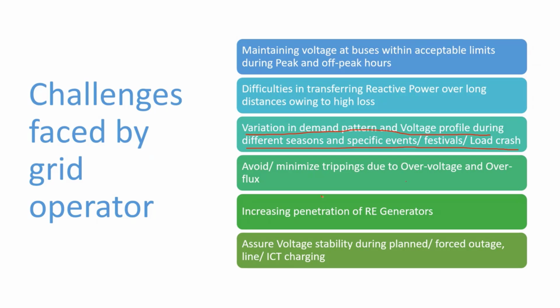Then this one is to avoid or minimize the tripping due to over voltage and overflux. If your transformer is operating at very high voltage and low frequency, then V/f protection is there to protect it, because there will be a very high external force on the winding of the transformer. This will result in deterioration or misalignment of the transformer itself. So that is a problem with the transformer. In the transmission system, you can face an over voltage situation which will stress the different equipment connected to the transmission system. That's why you have over voltage and overflux protection in the system, and the job of the operator is to avoid these operations, which are meant for when you face some severe contingency in the system, not for day-to-day operation. You want that lines should not trip on over voltage or transformers on overflux.